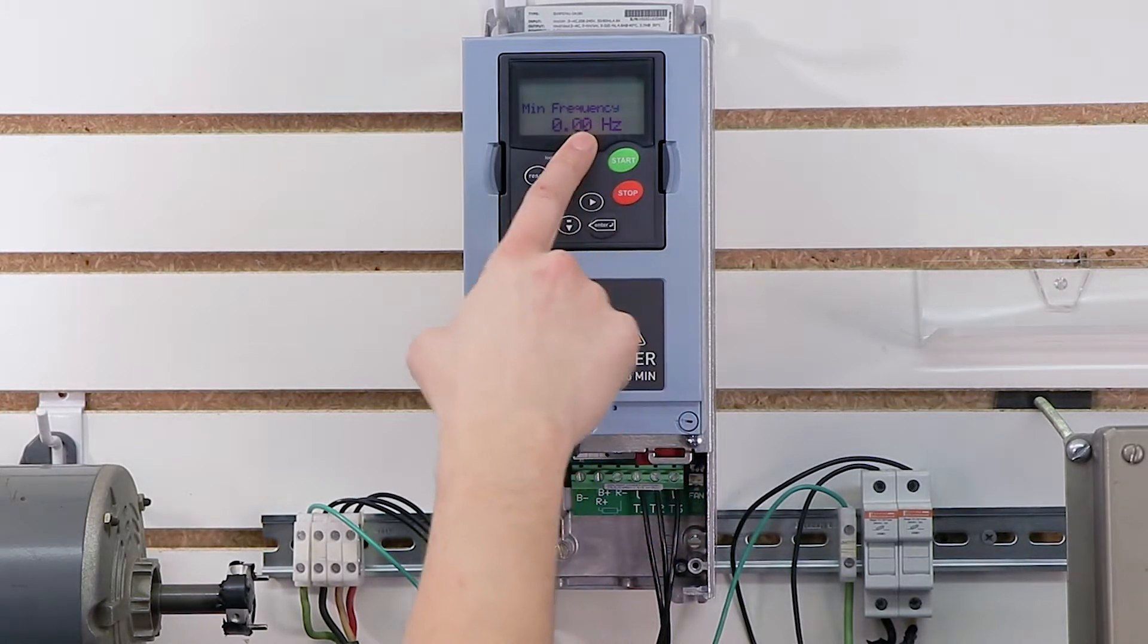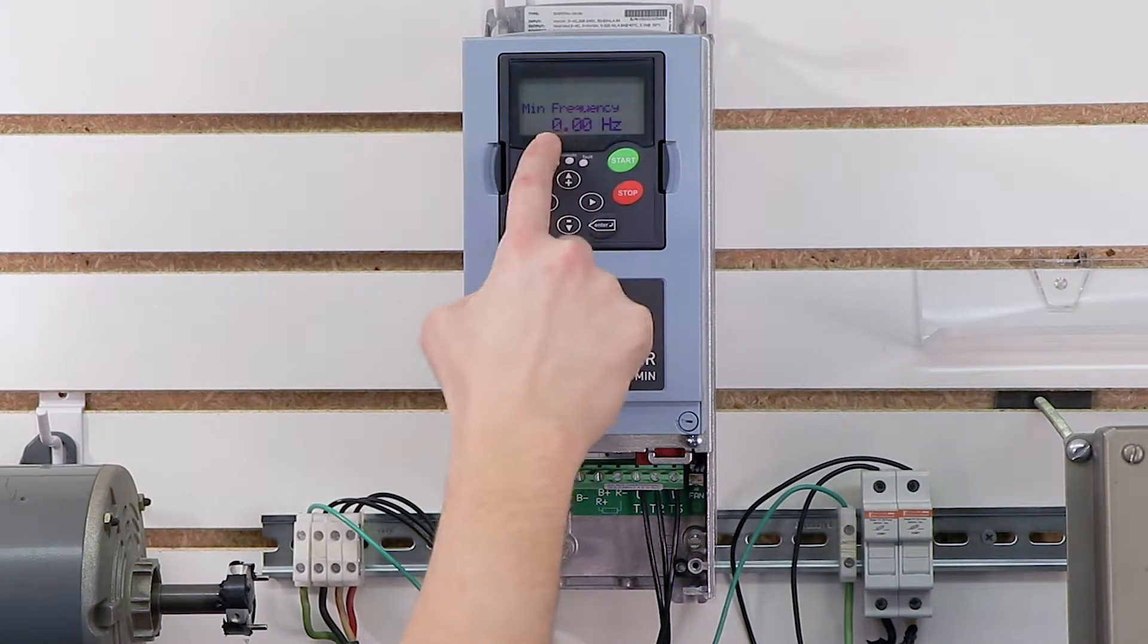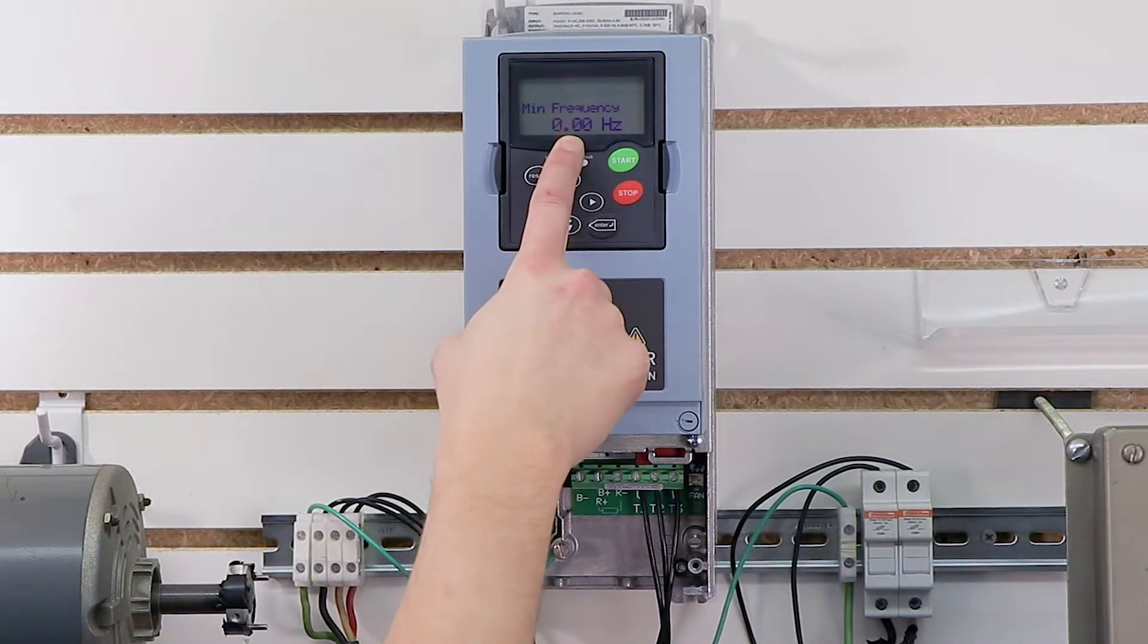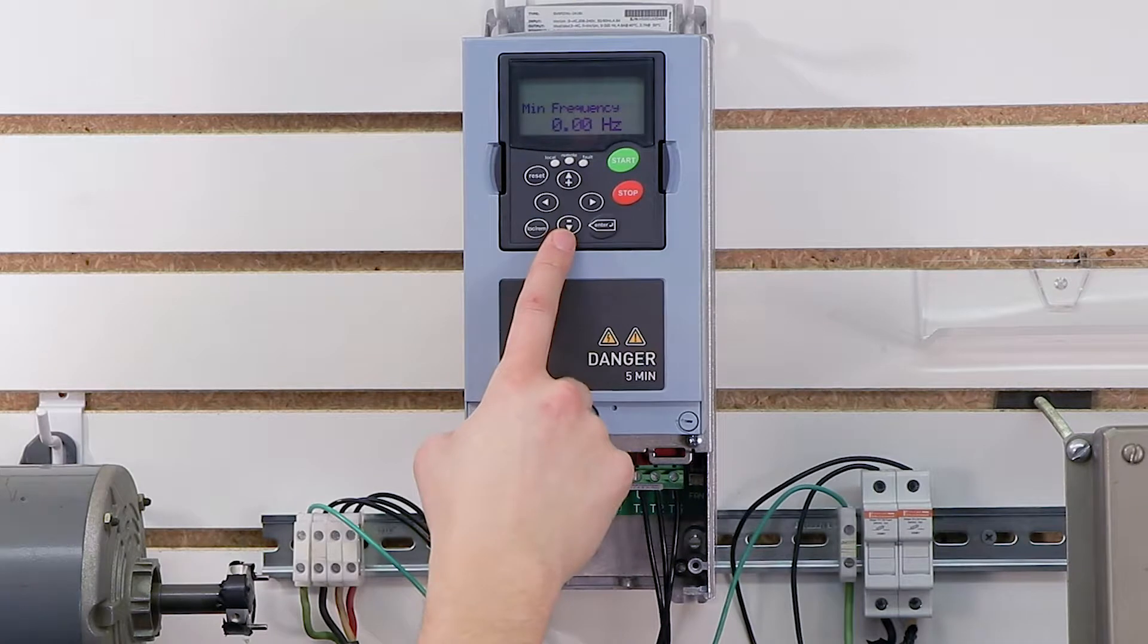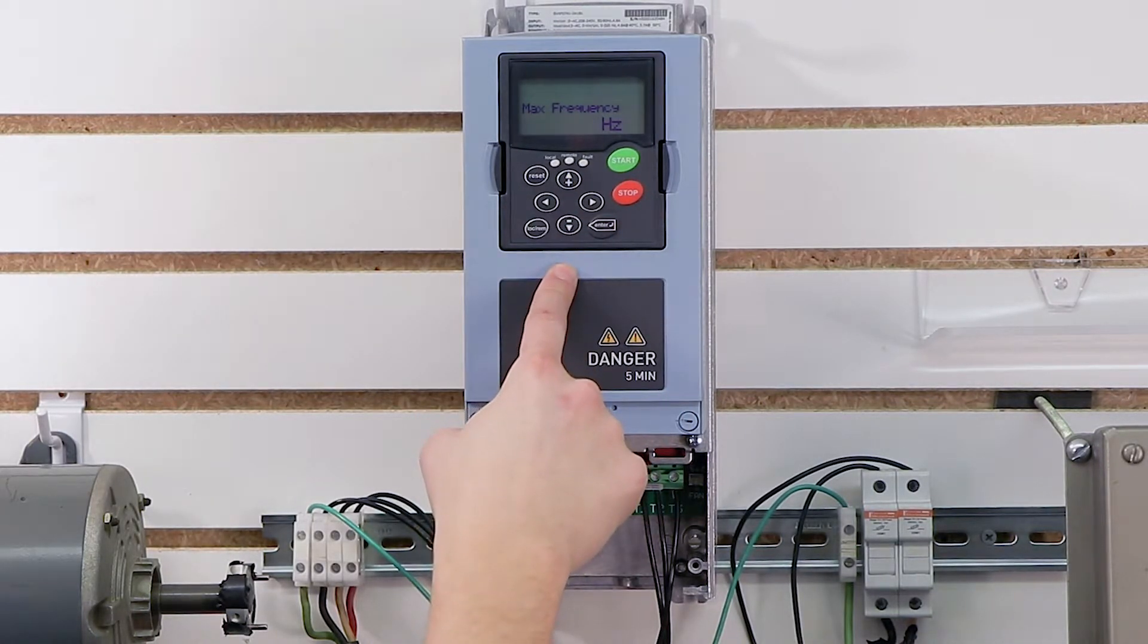Now I get to choose my minimum frequency. That's my minimum speed of my motor. If I wanted to say, for example, never run lower than 30 Hertz, I could set that here. But in my application, I'm going to leave it at zero so that I can actually stop the motor if I want to.